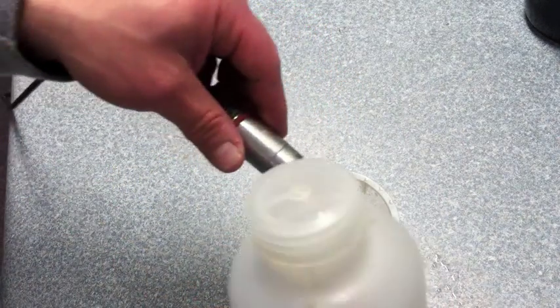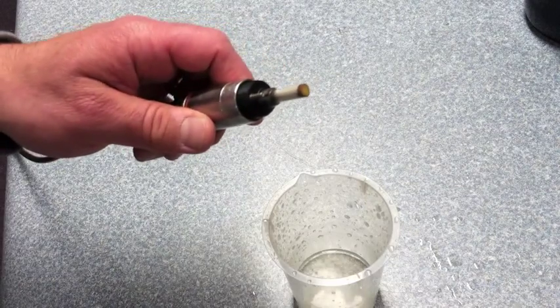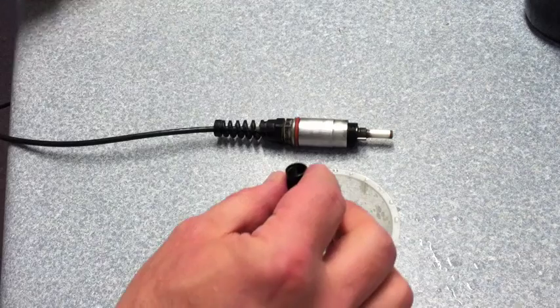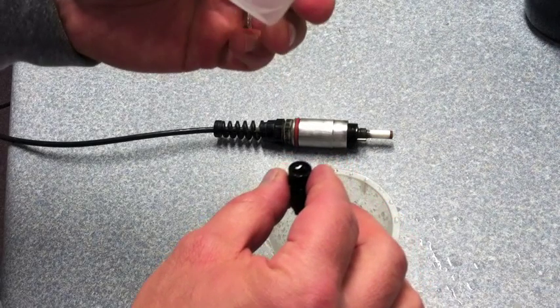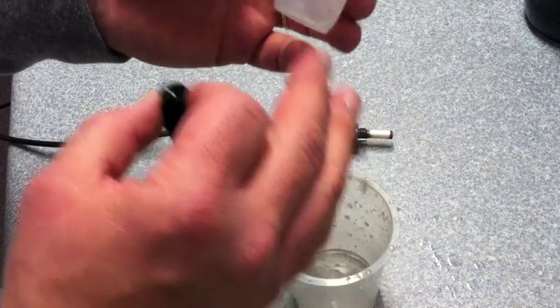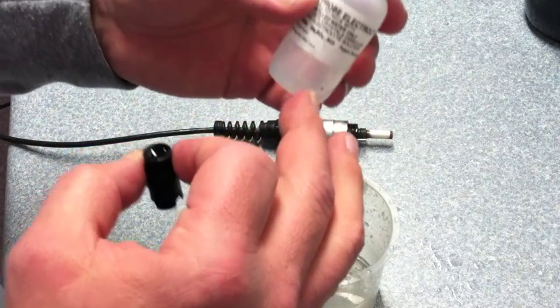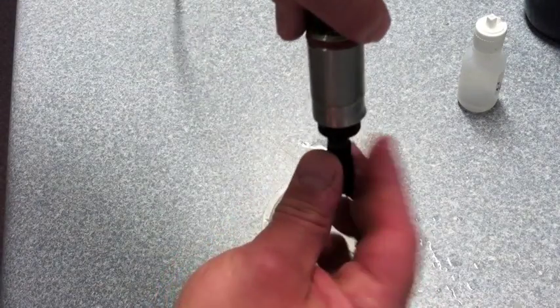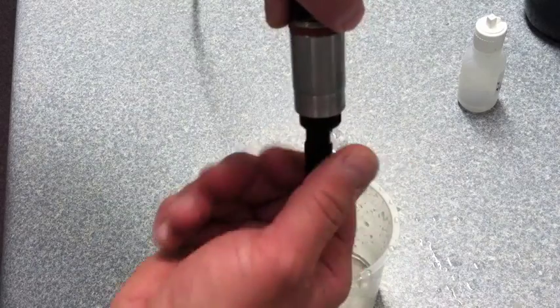And then as far as your cap installation, make sure you take a new cap and fill it with a fresh probe solution, electrolyte. Make sure that your solution once initialized with distilled water, it's not over a year old. And then you can just fill it up to the bottom of the cap and you can screw it back on.